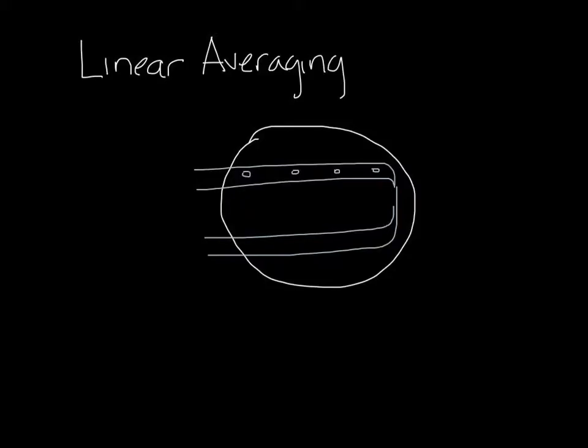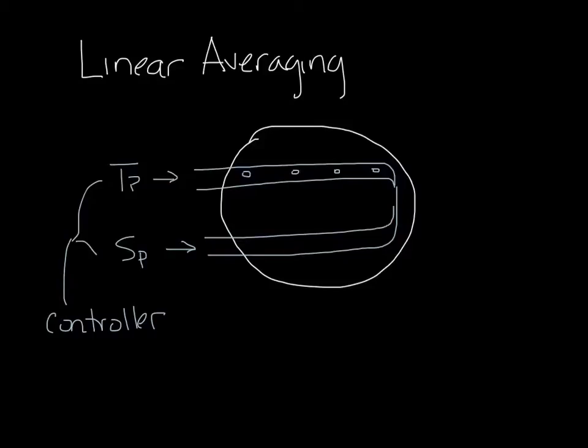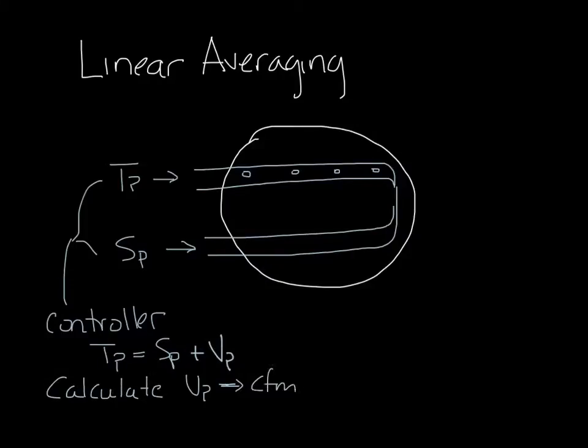So if you're looking into this flow sensor, and the airflow is going in the direction you're looking, the top one would be measuring total pressure, and the bottom one would be measuring static pressure. And then both of these are connected back to a controller. And if you remember, total pressure is static pressure plus velocity pressure, so the controller can use this information from the flow sensor to calculate velocity pressure, and therefore velocity, and therefore CFM.